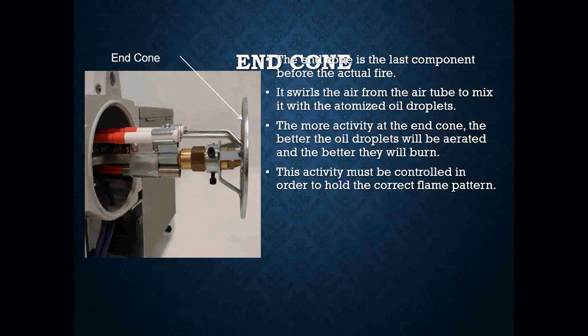Your end cone is the last component before the actual fire. It swirls the air from the air tube to mix it with the atomized oil droplets. The more activity at the end cone, the better the oil droplets will be aerated and the better they will actually burn. When servicing oil burners, we want to make sure the end cone is clean and not caked up with soot and debris, because if it is, you are not going to get a good swirling effect and the oil will not atomize and mix well, which will create a lot of soot and smoke. We want to make sure the end cone is in good condition to hold the correct flame pattern.